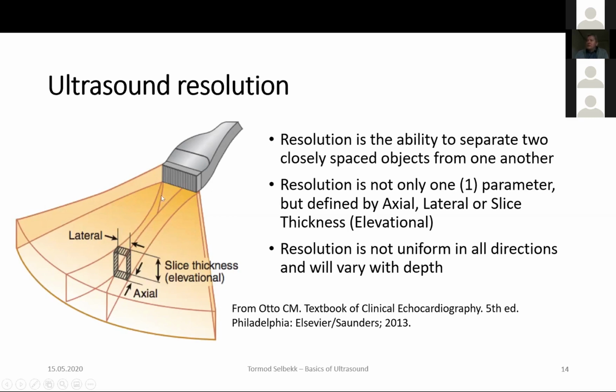And the resolution is not uniform in all directions, and it will vary with depth. So usually most transducers have a sort of sweet zone where you have the best image quality. So it's also important to select a transducer that actually has the optimal quality at the depth you're looking at.